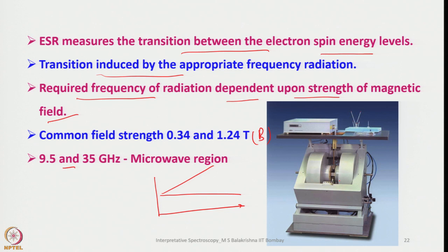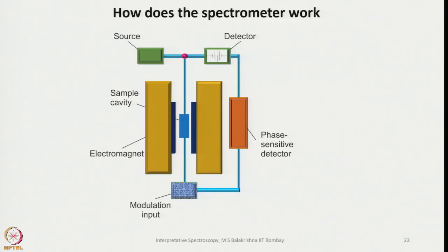This is how a typical EPR instrument looks: the magnetic field is here, the sample is kept here, and the signals go to the detector and then to the plotter for plotting the spectrum. The spectrometer has a source, a detector, a sample cavity, an electromagnet, a phase sensitive detector, and modulation input.